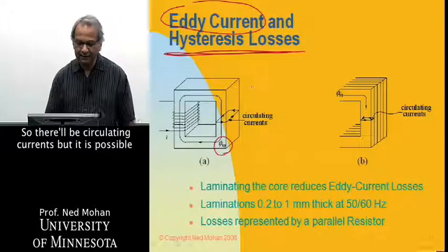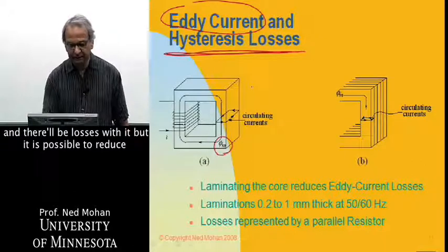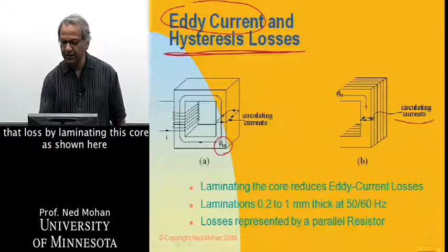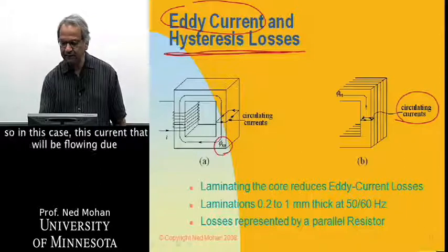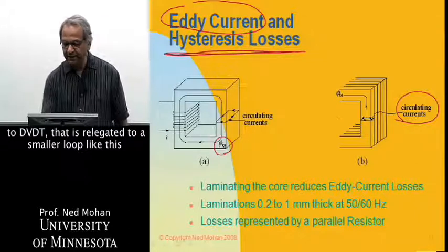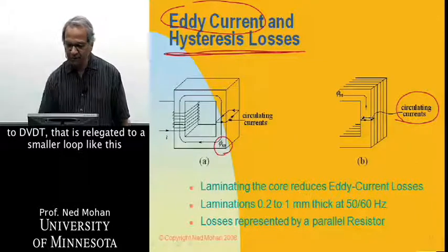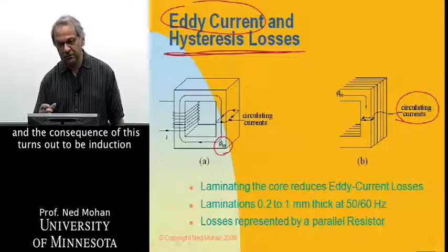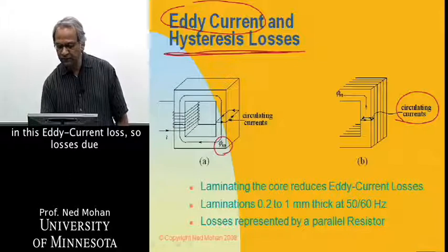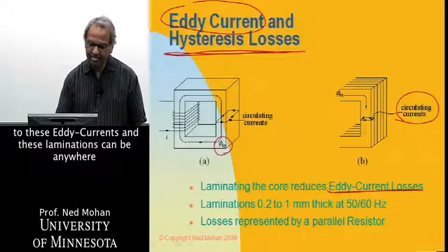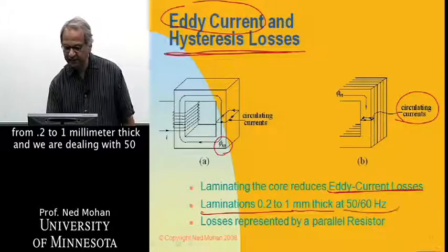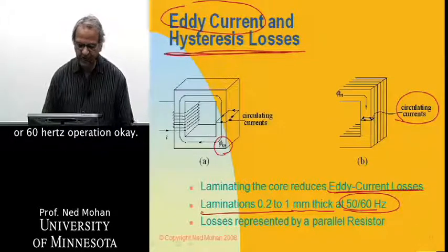So there will be circulating currents, and there will be losses with it, but it is possible to reduce that loss by laminating this core, as shown here. So in this case, this current that will be flowing due to dΦ/dt is relegated to a smaller loop like this. And the consequence of this turns out to be reduction in this eddy current loss. So our loss is due to these eddy currents. And these laminations can be anywhere from 0.2 to 1 millimeter thick when we are dealing with 50 or 60 hertz operation.